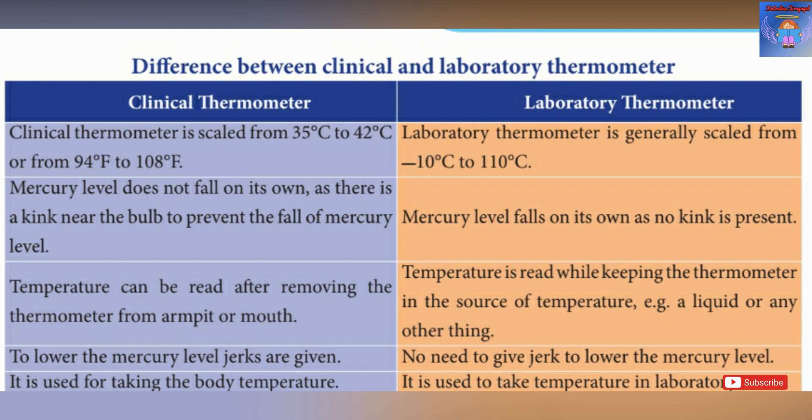Now the difference between clinical and laboratory thermometers. The clinical thermometer ranges from 35 degrees Celsius to 42 degrees Celsius (94 to 108 degrees Fahrenheit). The laboratory thermometer ranges from minus 10 to 110 degrees Celsius. In a clinical thermometer there is a kink that prevents mercury from falling back; in a laboratory thermometer there is no such kink. The clinical thermometer requires jerking; the laboratory thermometer does not.